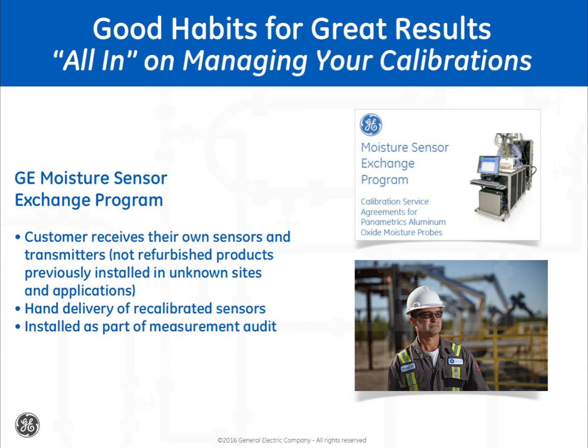The greatest success occurs when a more intimate relationship exists between the vendor and the customer. This is when customers ask us to hand-deliver recalibrated sensors and install them and inspect the system as part of a complete measurement audit. The GE service engineer will then return the customer's sensors to the service center, segregated from other customer sensors, where the sensors await their future calibration and return to process. In these cases, the customer and the manufacturer share ownership in the success of these moisture measurements.